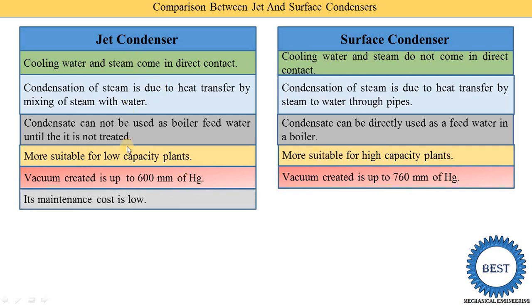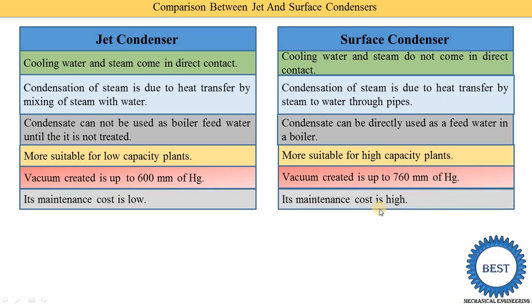In a jet condenser, the maintenance cost is low. In a surface condenser, the maintenance cost is high. The reason maintenance cost is high is because in a surface condenser there are a number of pipes, and fouling occurs — the pipes get fouled after some time. So we need to do proper cleaning of the pipes, which is why the maintenance cost is increased.